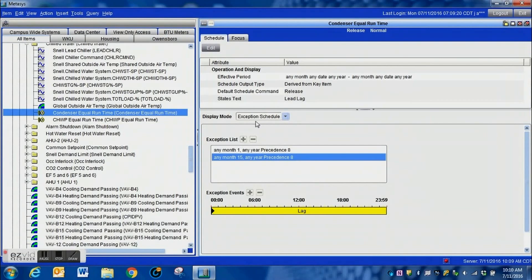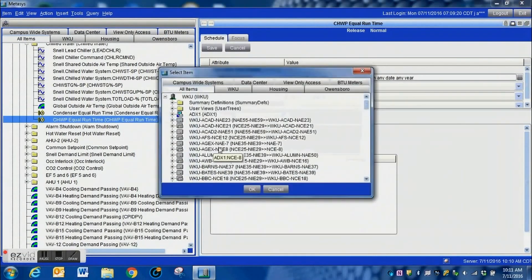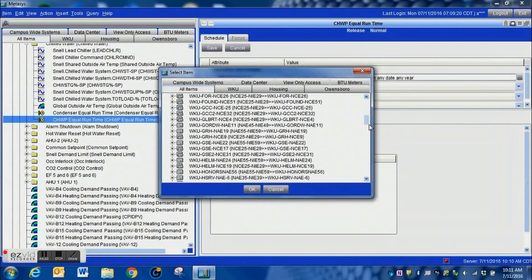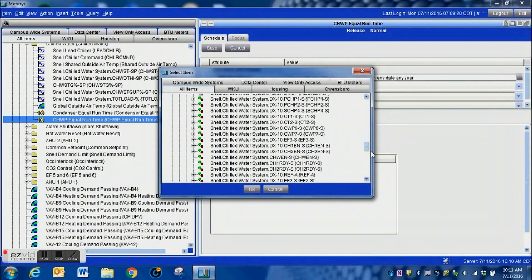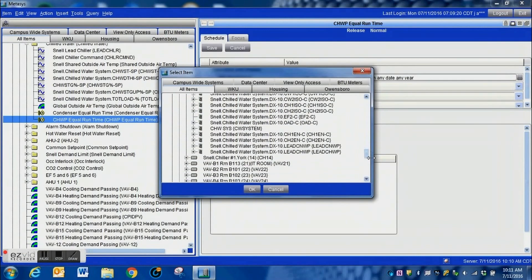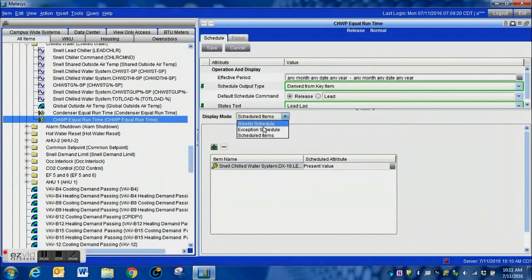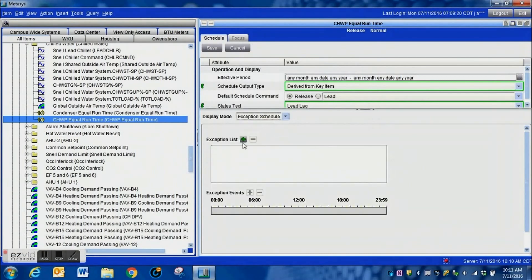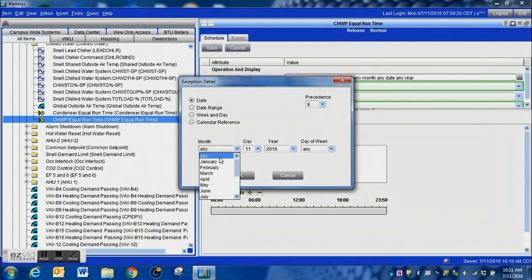You can set it up to where it's even and odd months like I've mentioned before, but this is a very effective way to automatically rotate your pumps. Here we are on the primary pump schedule, kind of the same principle. We drill down under our selected item schedule, we hit the lead lag switch, we bring that in and we have now bound that to the primary pumps.